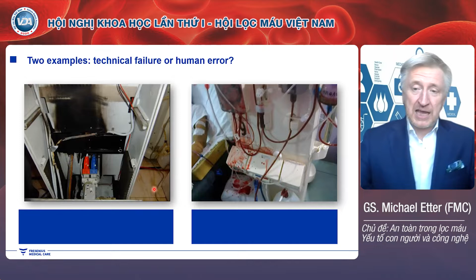So this picture here on the left-hand side was actually a fire inside a dialysis machine, a very dangerous situation after a short circuit on an electrical board. But this was not because the machine did something wrong. It is because the technical staff who was cleaning didn't follow the instructions, and water went into the housing of the machine and created this problem. So you can see there is very often a link between the technology and the human factor.